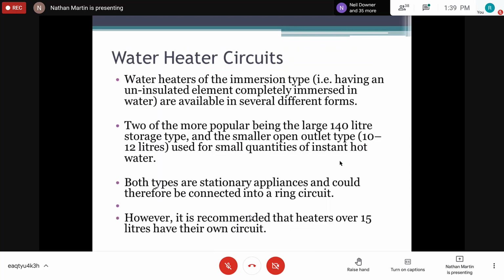Now, water heaters. Water heaters of the immersion type, such as the ones used in most residential and commercial settings, are available in several different forms. Two of the more popular types are the 140 liter and the 10 to 12 liter, used for quantities of instant hot water. So these are the ones that we use in our homes, the electric type. Both types are stationary appliances, so they are classified as stationary appliances and should be treated in a certain way. It's recommended that heaters over 15 liters have their own circuit. So we're talking about water heaters with capacity greater than 15 liters.